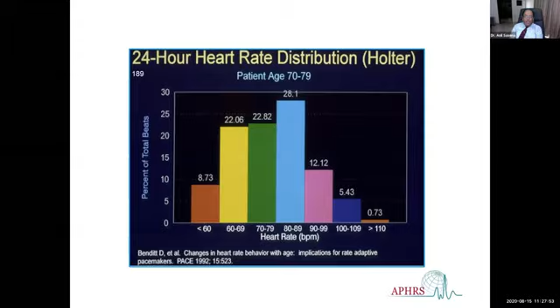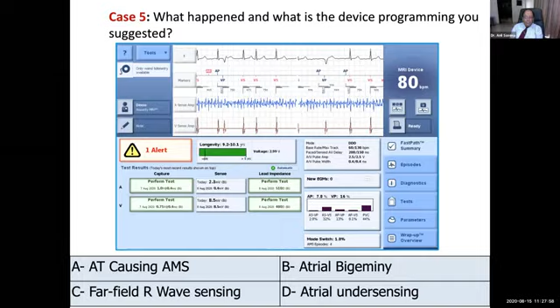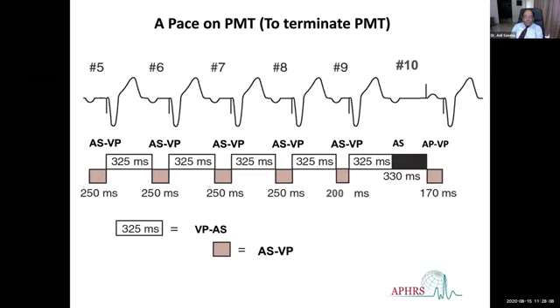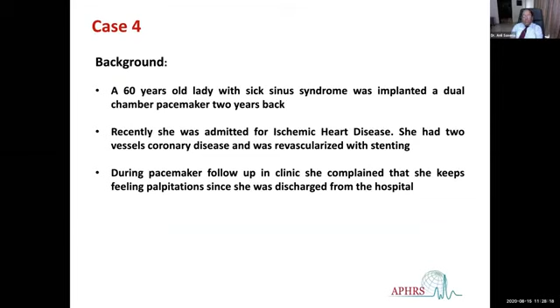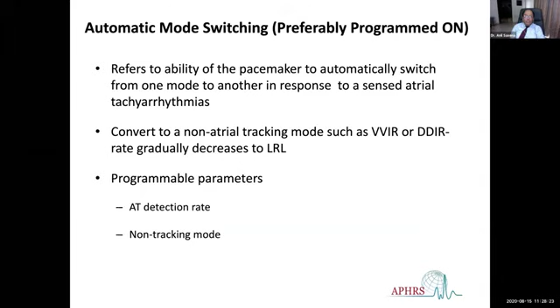DDI, yeah. So I can go back to the case. We know the meaning of these letters. The first letter represents the chamber that is paced. So in a dual chamber DDD or DDI, the first letter indicates that both chambers are paced. The second letter is also D, which indicates that both chambers are sensed. And the third letter D means a dual response. So when the pacemaker senses an atrial signal, it will inhibit the atrial pacing, but it will trigger ventricular pacing.